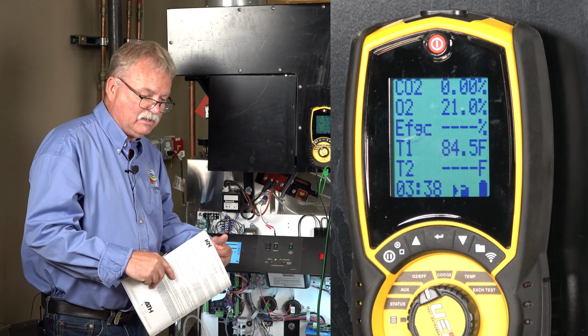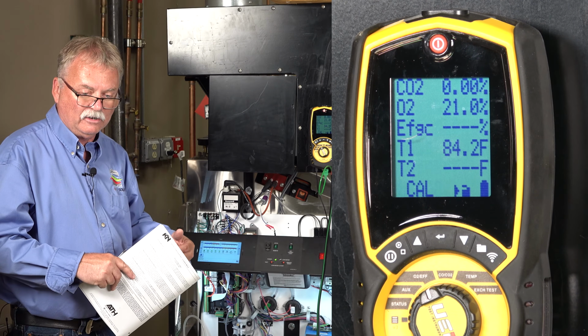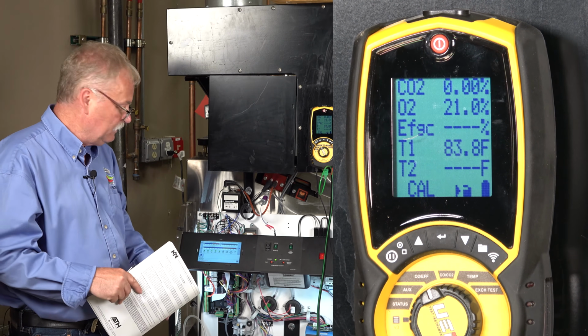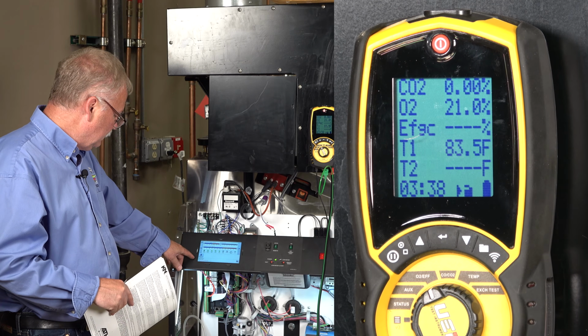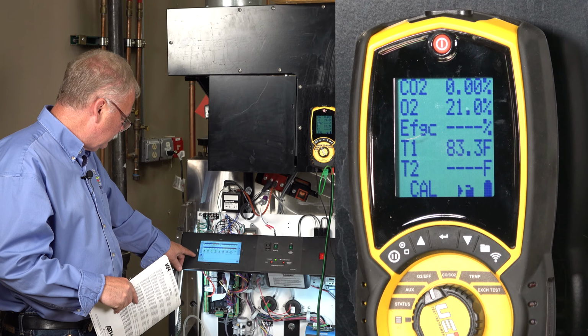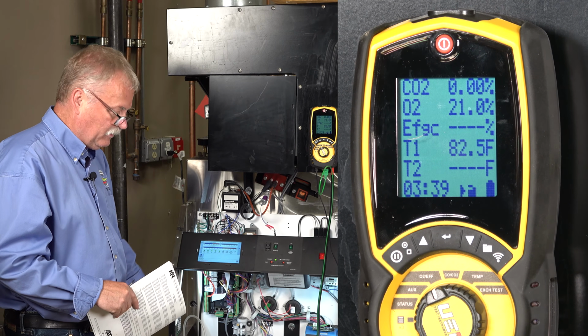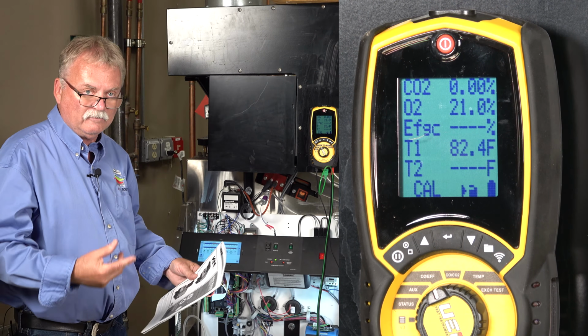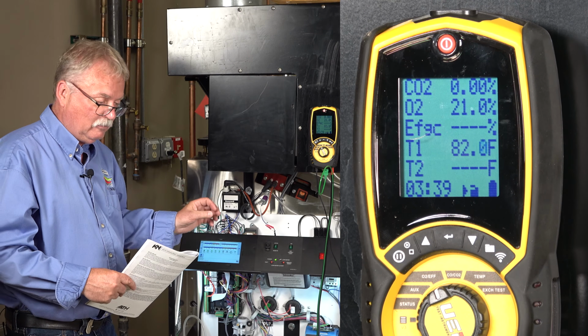Why does it do that? Because you don't fire it off at low fire. It's a very unstable flame. Fire it off in the middle. Picking up a little bit of noise. Let's see what happens if it goes away. Yep, it went away. So that's the first official light off of that boiler. Made a little bit of noise.